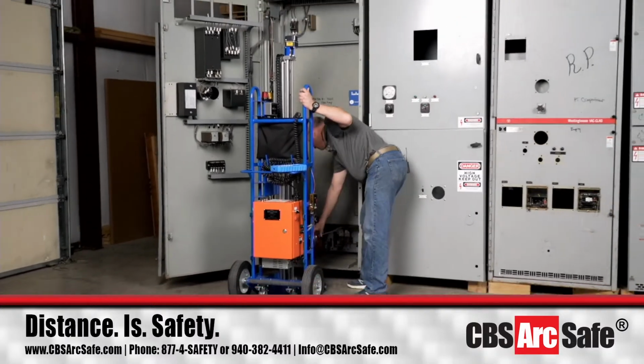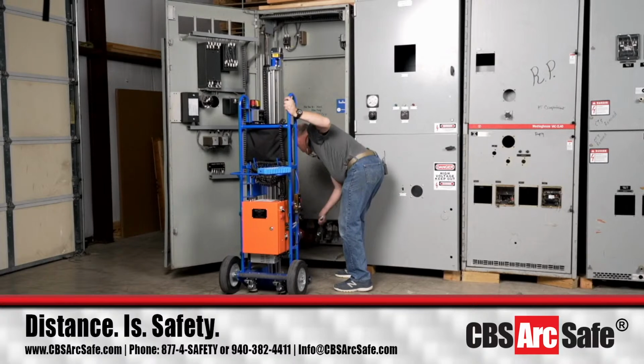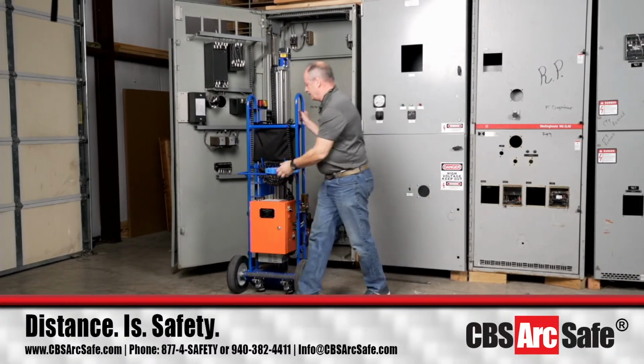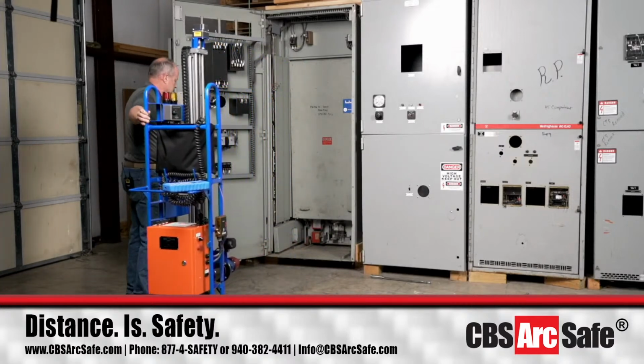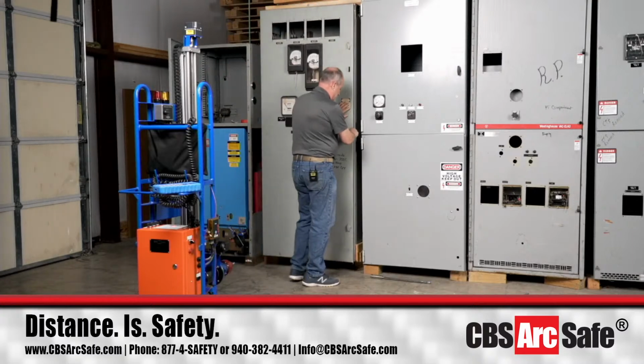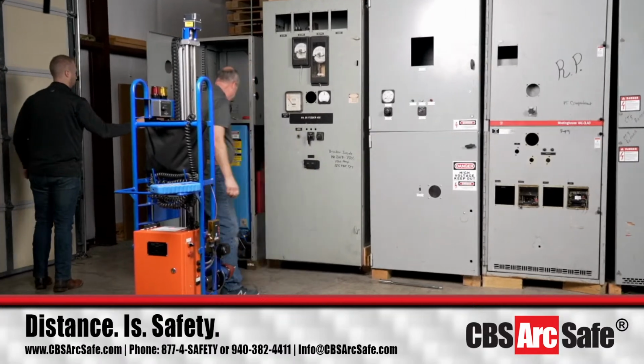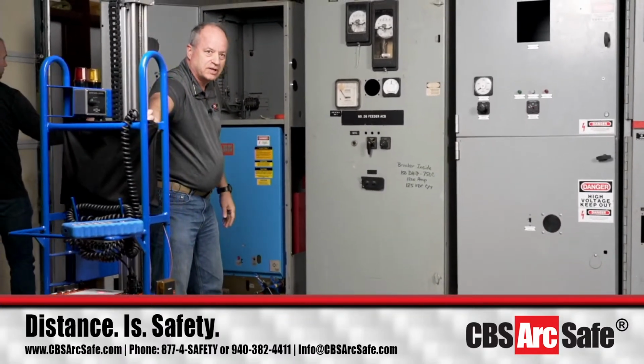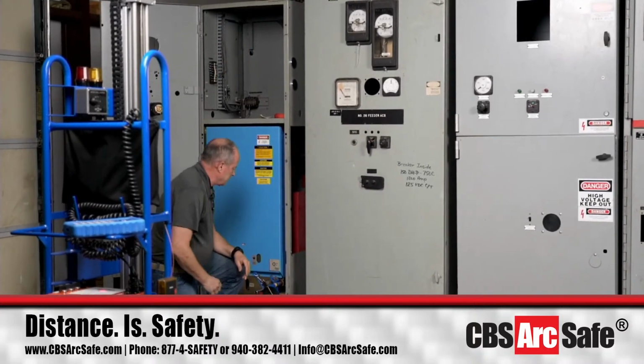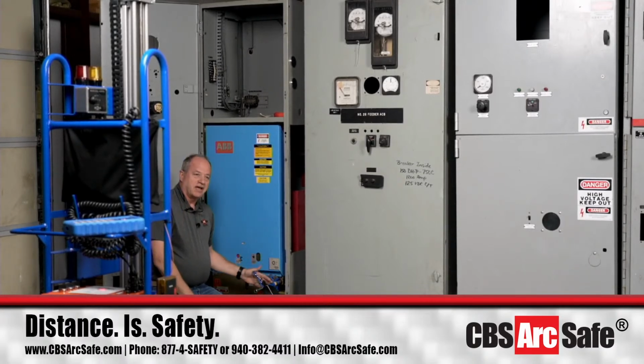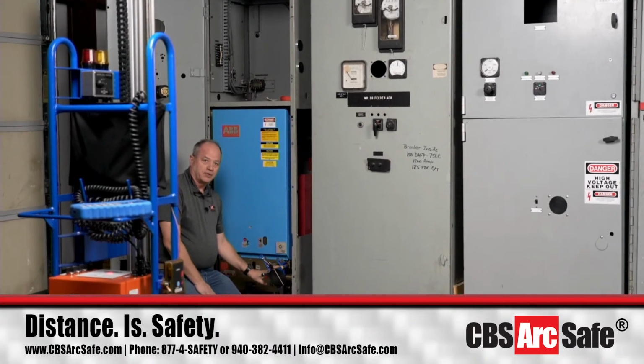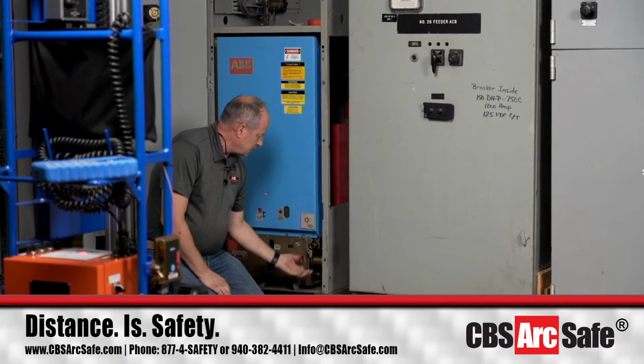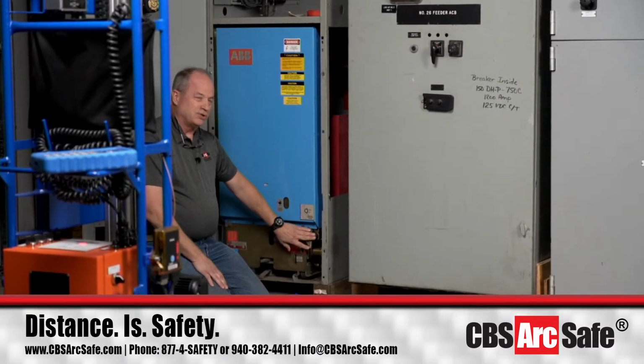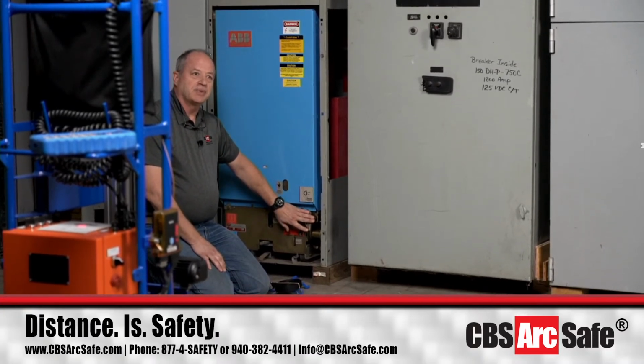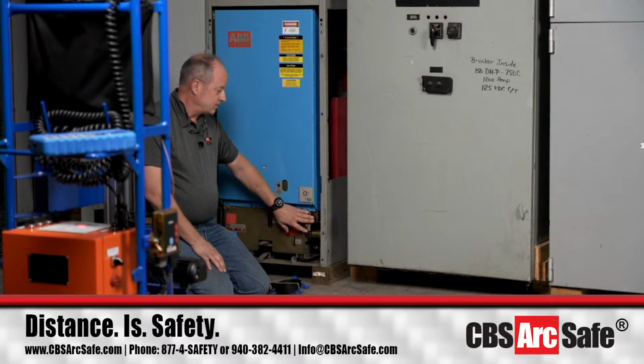This time I'll do it the easy way from the front. Okay, a couple things I want to talk about before I get the RRS-1 hooked up to this are the HK family. So the racking mechanism on a 5 HK and a 15 HK are similar in terms of the latch to feet right here and the fact that you use the same racking tool. If you get to an HK 1000, it's a bigger breaker and a different tool. If you get to an HK 38, then it's even bigger. Okay, so those are things to understand.